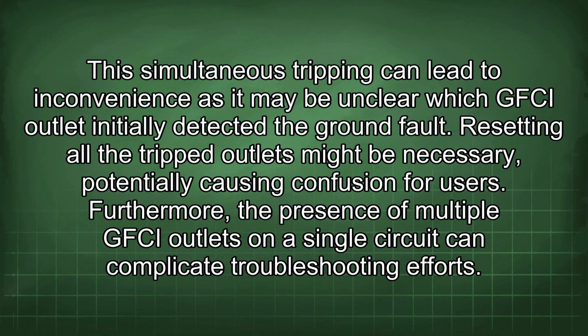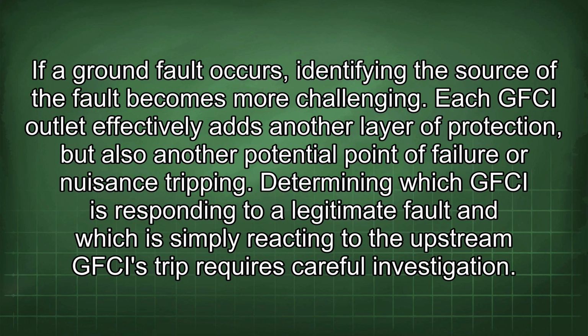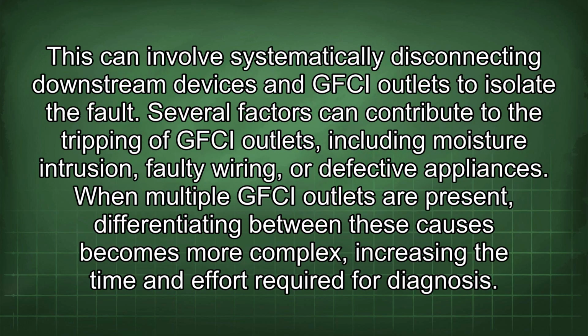Furthermore, the presence of multiple GFCI outlets on a single circuit can complicate troubleshooting efforts. If a ground fault occurs, identifying the source of the fault becomes more challenging. Each GFCI outlet effectively adds another layer of protection, but also another potential point of failure or nuisance tripping. Determining which GFCI is responding to a legitimate fault and which is simply reacting to the upstream GFCI's trip requires careful investigation. This can involve systematically disconnecting downstream devices and GFCI outlets to isolate the fault.